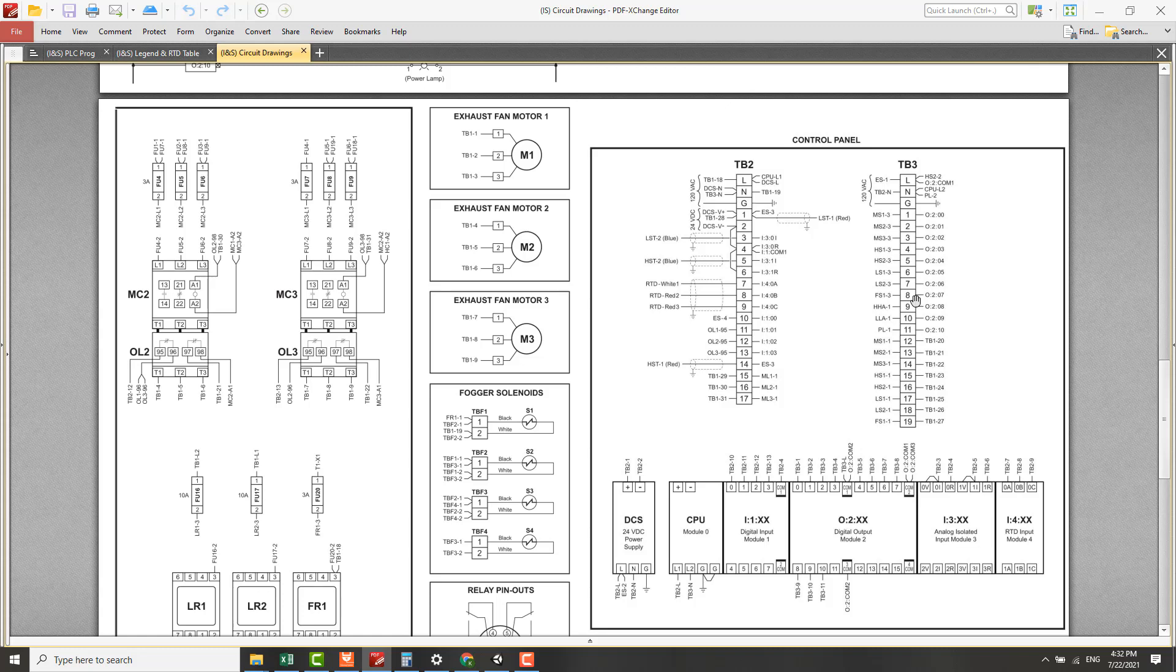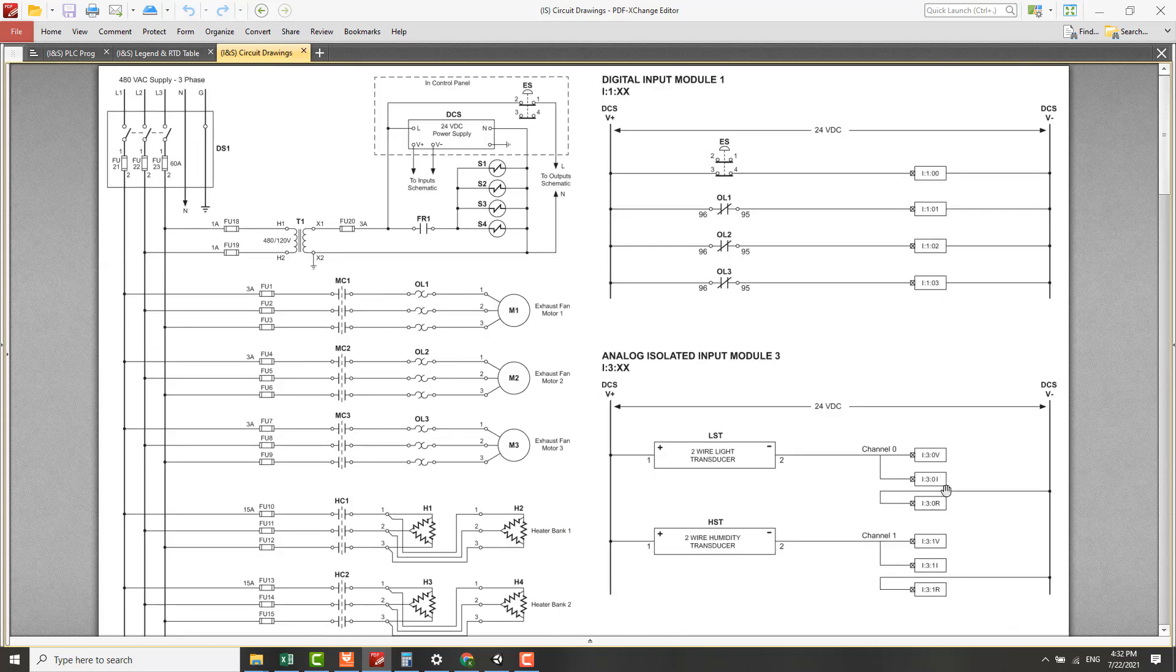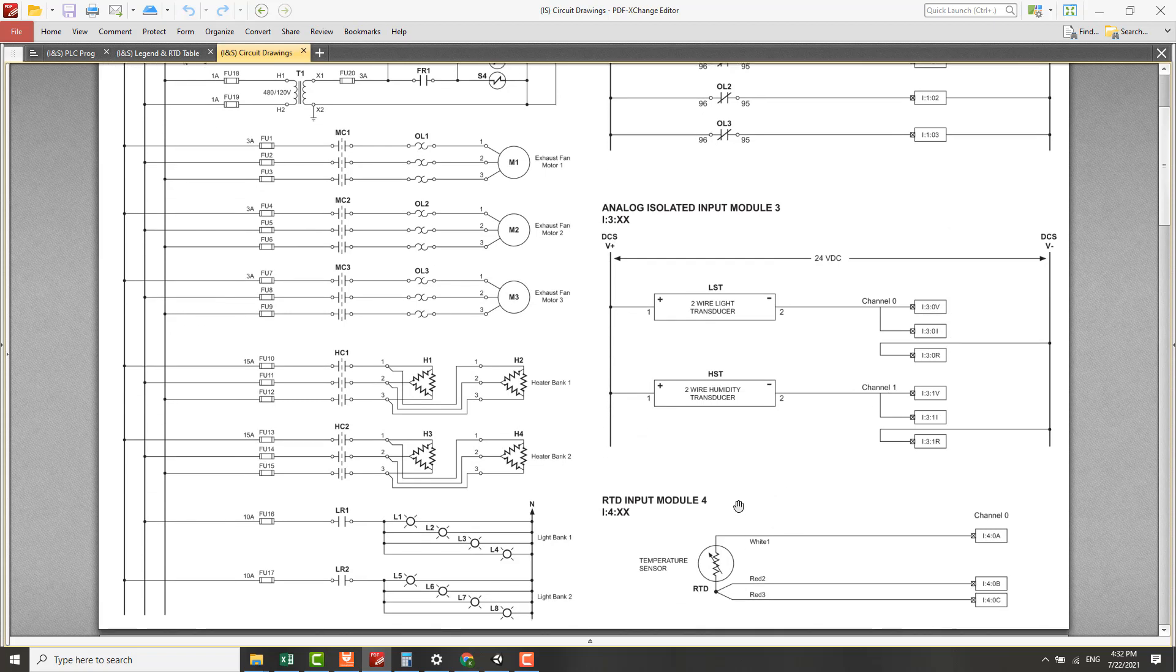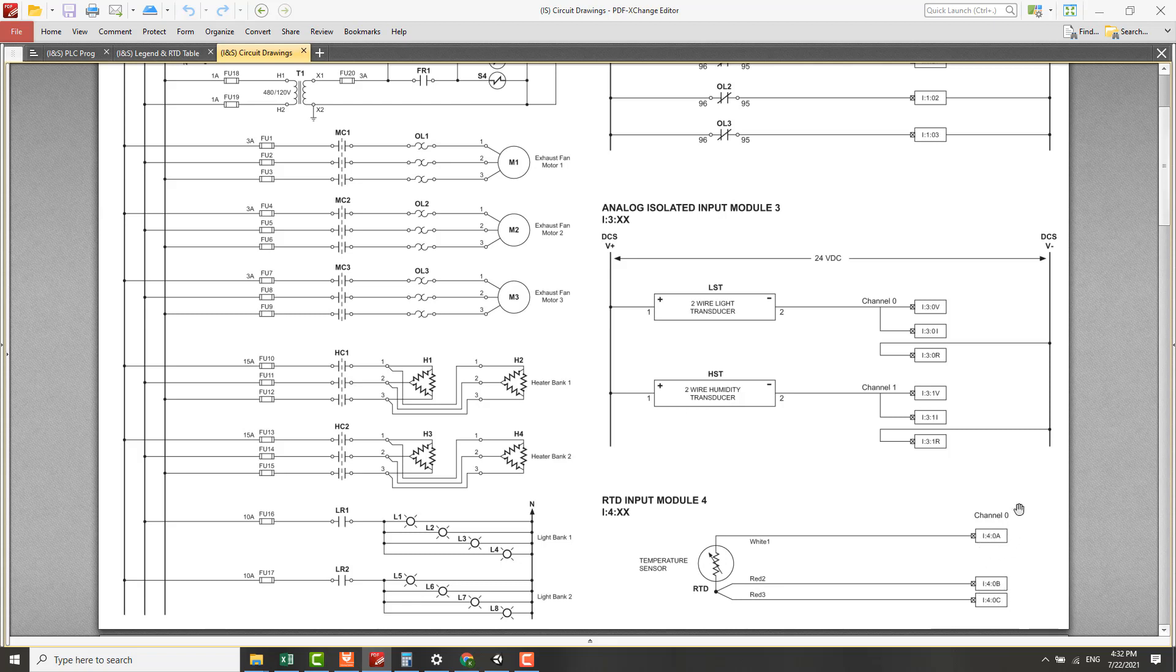We know that something's wrong with the temperature RTD. The temperature detected at the PLC analog input RTD module number 4 channel 0, the voltage detection should be low as we saw just now - zero degrees. It means the resistance here is very low, thus the voltage is low, which is abnormal because the local temperature should be 42 but it only gives a very low voltage. That's why it detects wrongly. Either the PLC analog input RTD module card 4-0 or the RTD is having an internal short circuit.